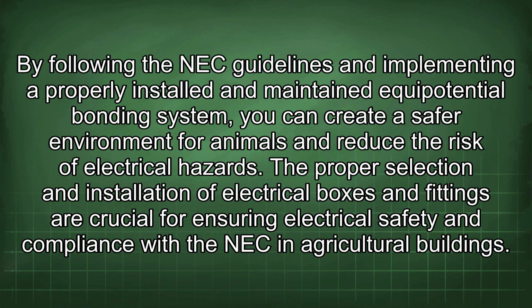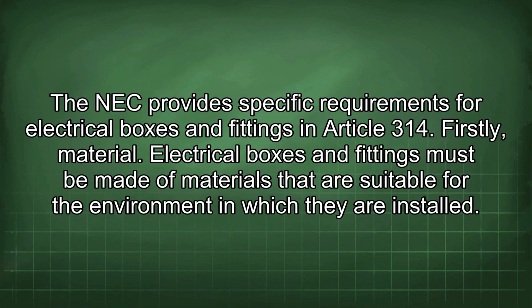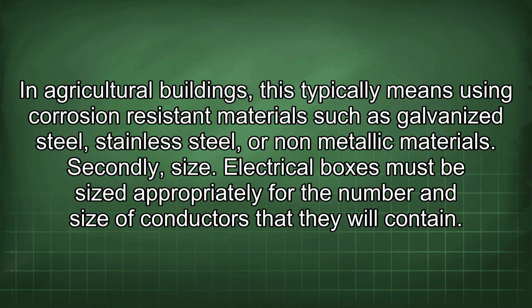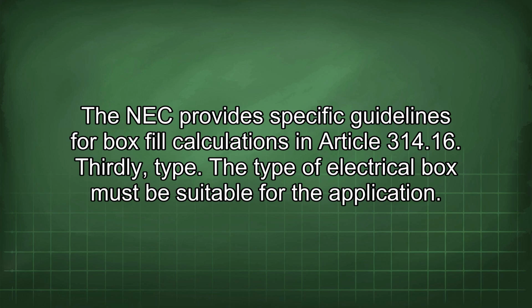The proper selection and installation of electrical boxes and fittings are crucial for ensuring electrical safety and compliance with the NEC in agricultural buildings. The NEC provides specific requirements for electrical boxes and fittings in Article 314. Firstly, material. Electrical boxes and fittings must be made of materials that are suitable for the environment in which they are installed. In agricultural buildings, this typically means using corrosion-resistant materials such as galvanized steel, stainless steel, or non-metallic materials. Secondly, size. Electrical boxes must be sized appropriately for the number and size of conductors that they will contain.